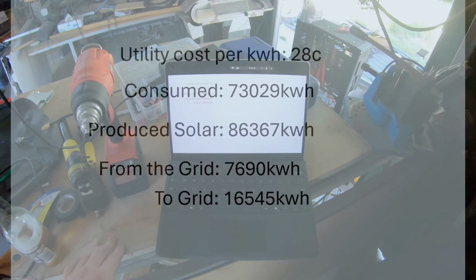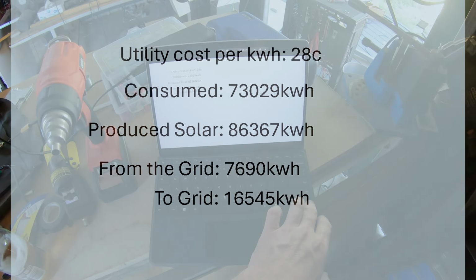Jesus, man, that's a lot. And then the produced solar was 86,367 kilowatt hours. From the grid, the bore pump pulled in 7,690 - the bore pump's a bit of a monster, so that's to be expected. What we sent to the grid was 16,545. So that's a 5.5 kilowatt system just bashing in power day in and day out.